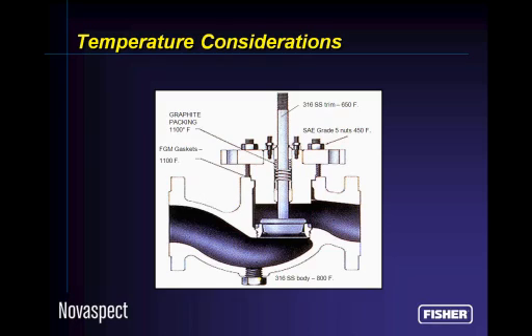And not every part in the valve has exactly the same temperature characteristics, so any valve that we pick, we have to look at what is the temperature capability of the part in there that has the lowest temperature and make sure that at least that one is above the design temperature for the valve.